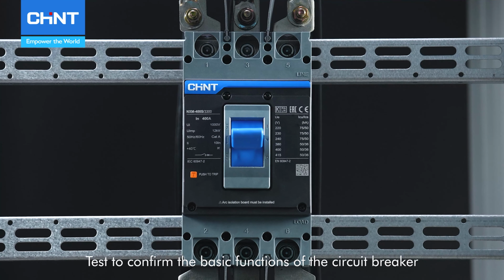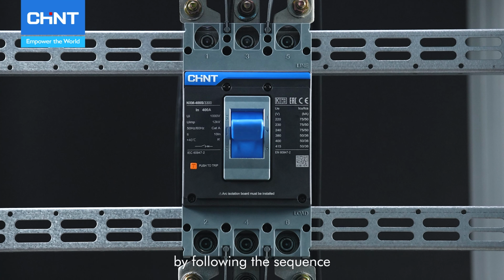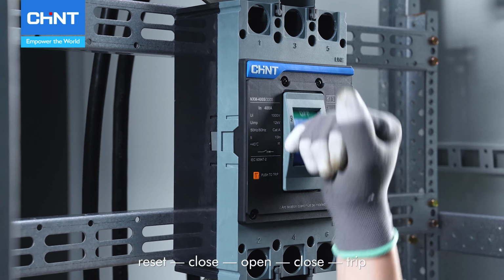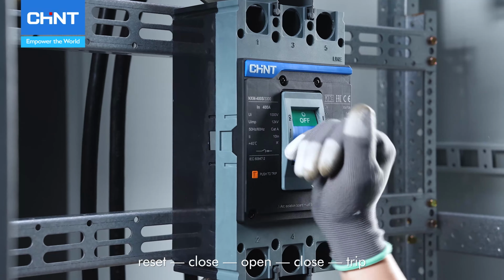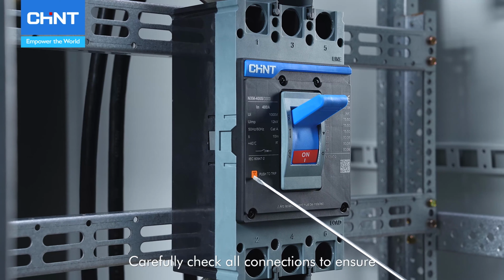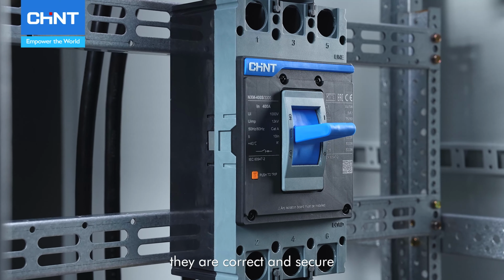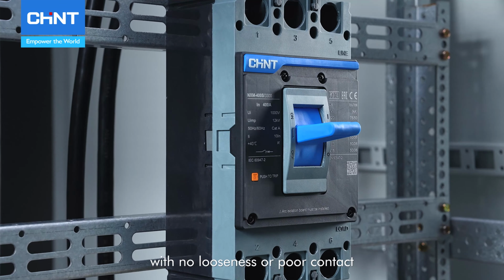Test to confirm the basic functions of the circuit breaker by following the sequence: reset, close, open, close, trip. Carefully check all connections to ensure they are correct and secure, with no looseness or poor contact.